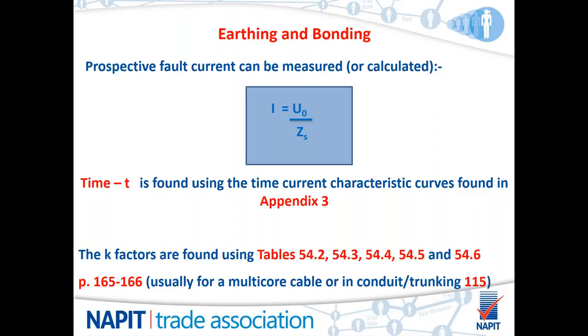The K factors can be found using tables 54.2, 54.3, 54.4, 54.5, and 54.6. Now these are on pages 165 to 166. And they are usually for a multicore cable or in conduit trunking, 115.